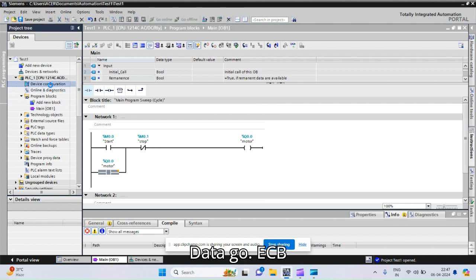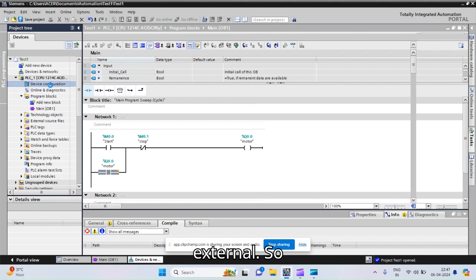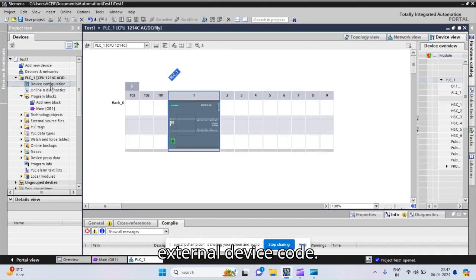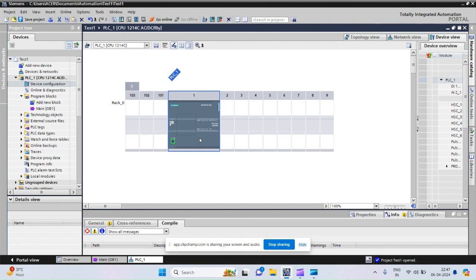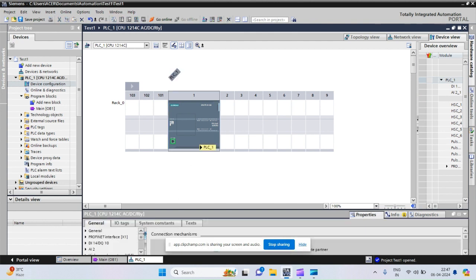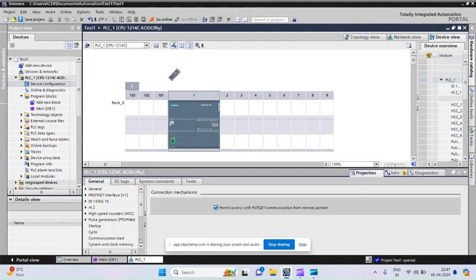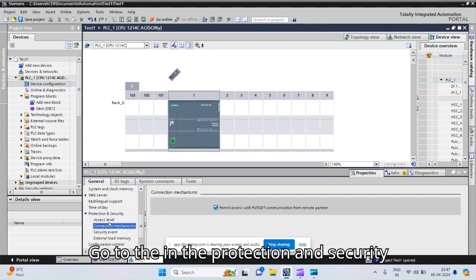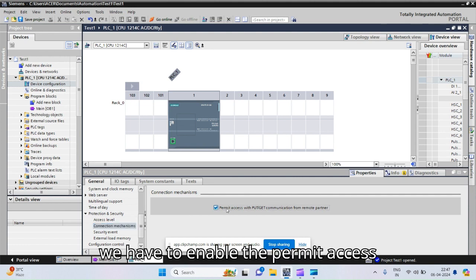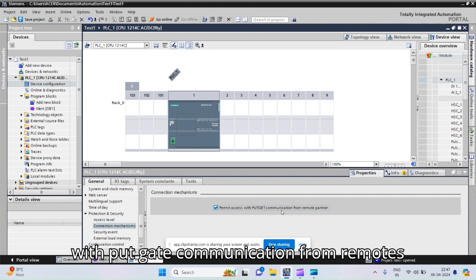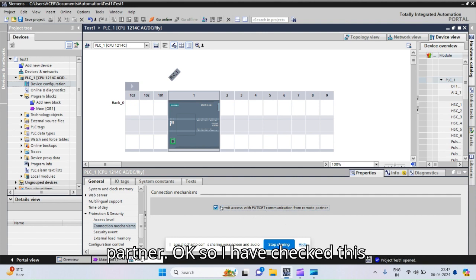To connect an external device, go to external device settings. Click on the PLC hardware section. In the protection and security, go to the connection mechanism and enable 'Permit access with PUT/GET communication from remote partner'. OK, so I have checked this.